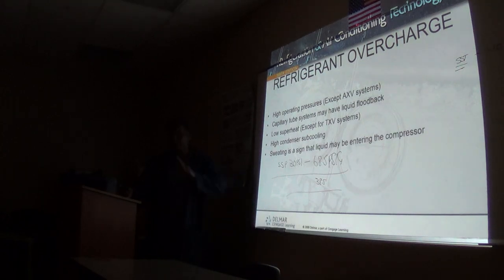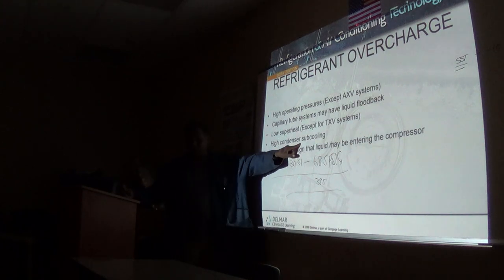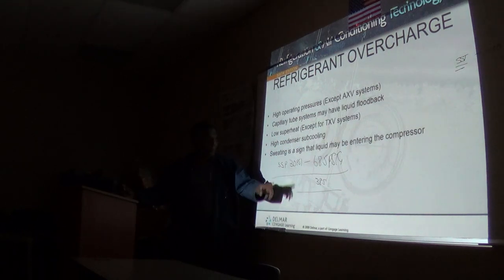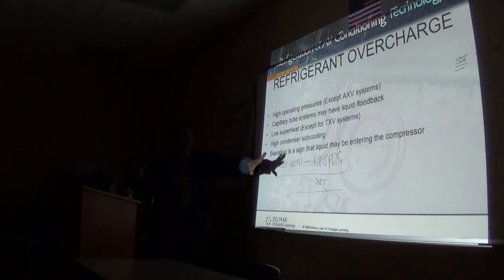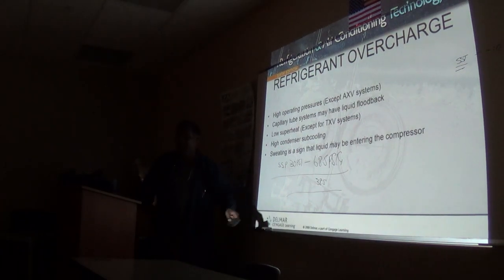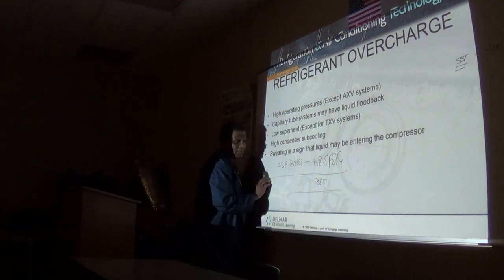So, overcharge, guys, one thing you must remember with an overcharge: when you check subcooling, it's very high. When we come back from the break, I'm going to explain that, because that's something a lot of people don't grasp. When it's overcharged, you have a high sub.